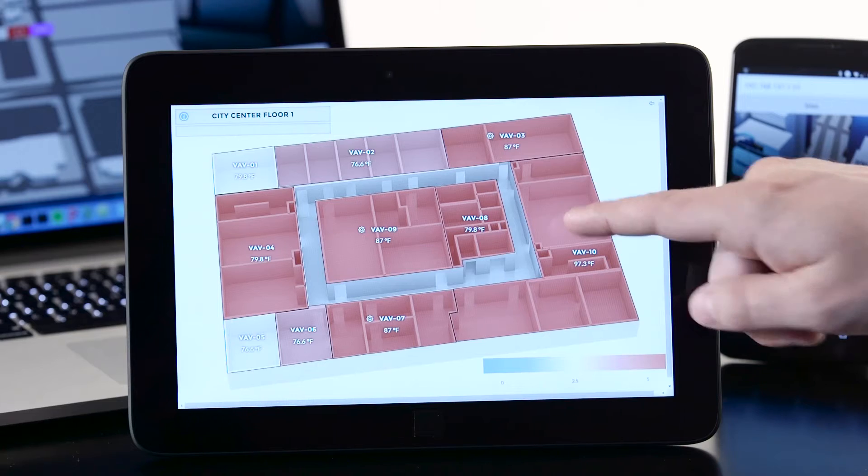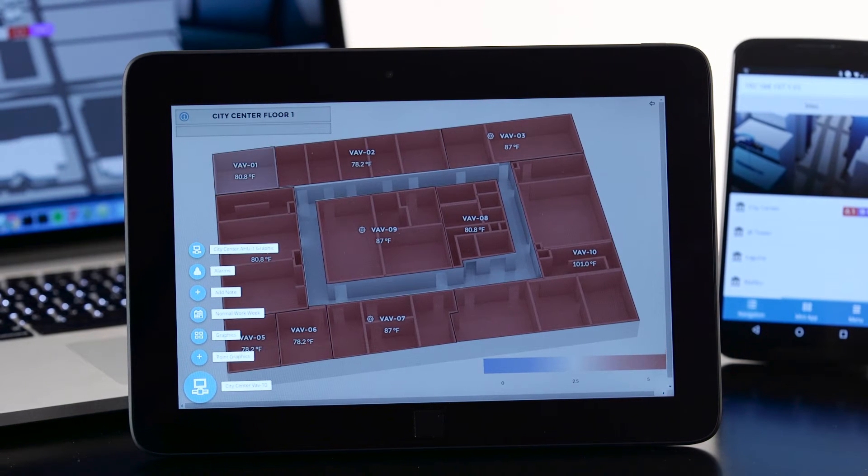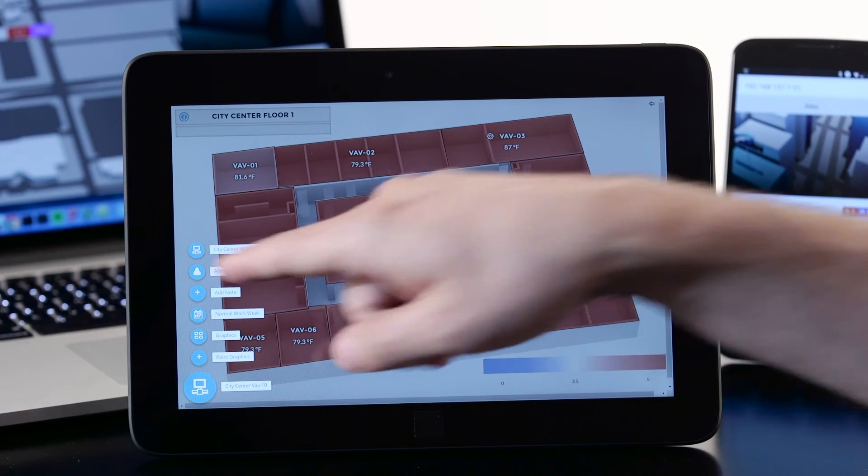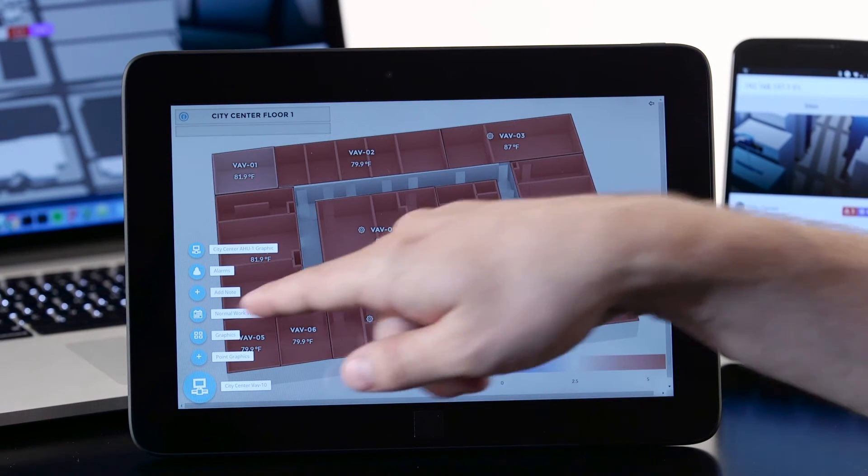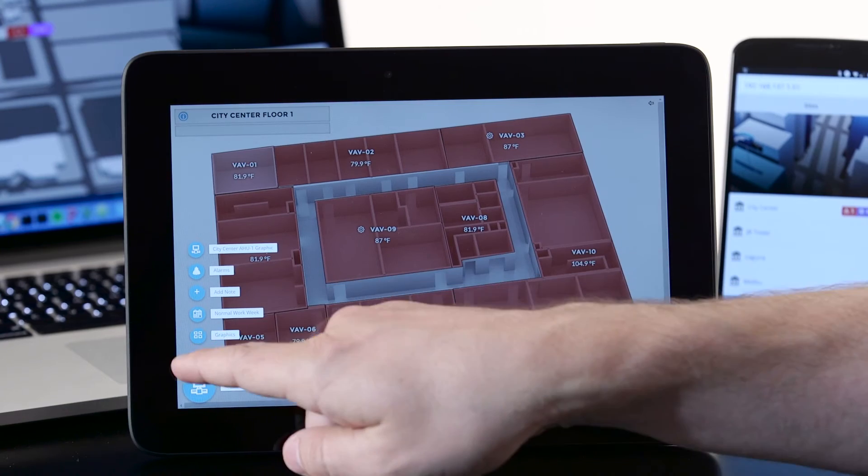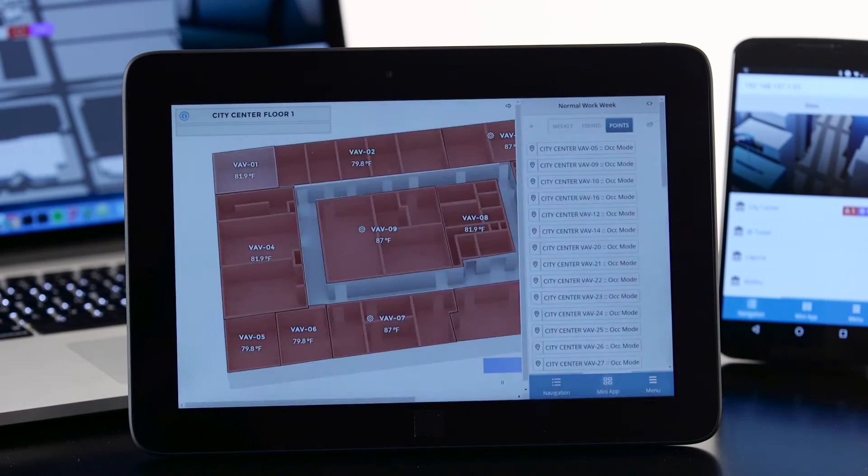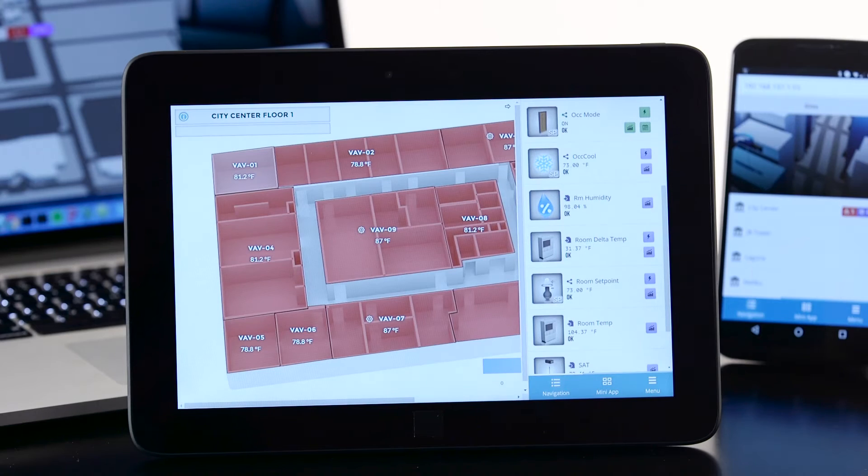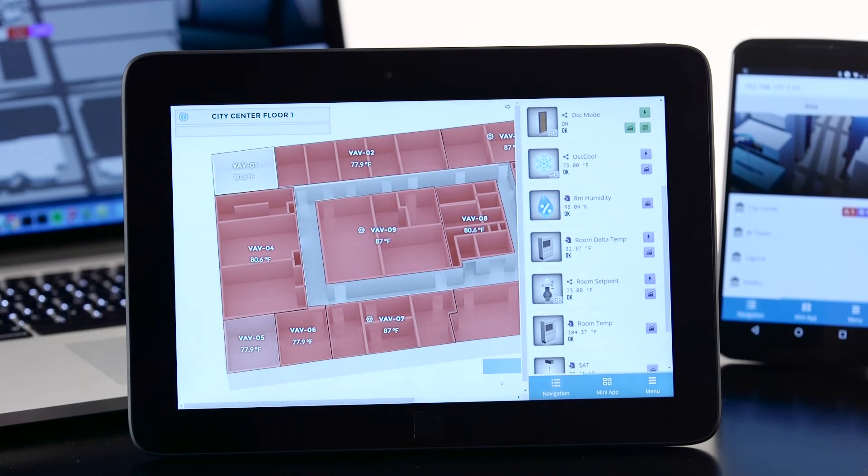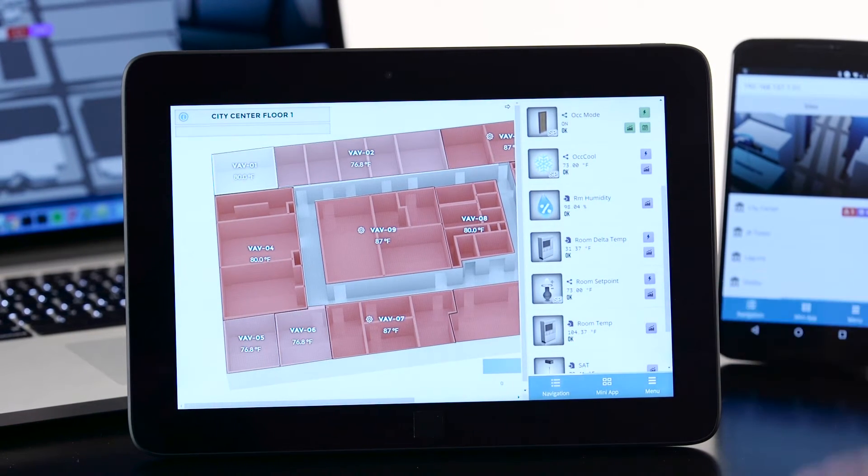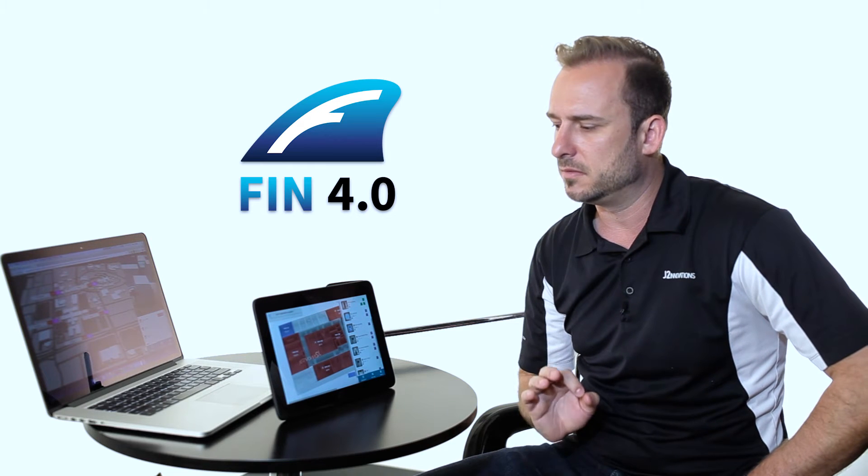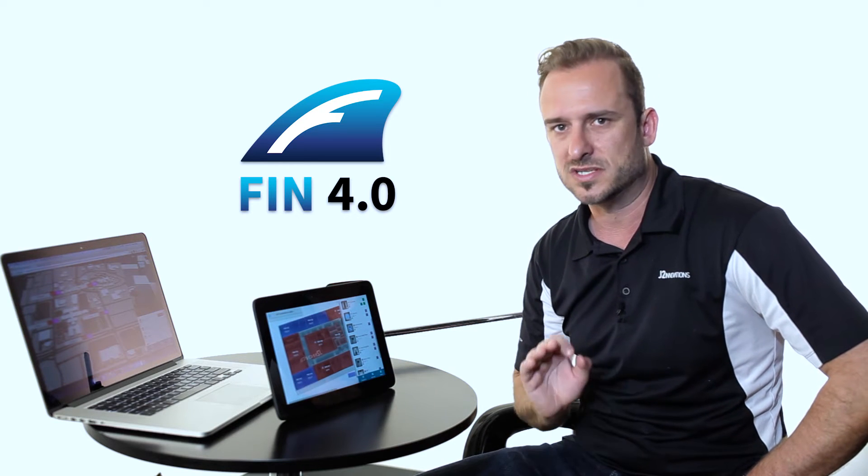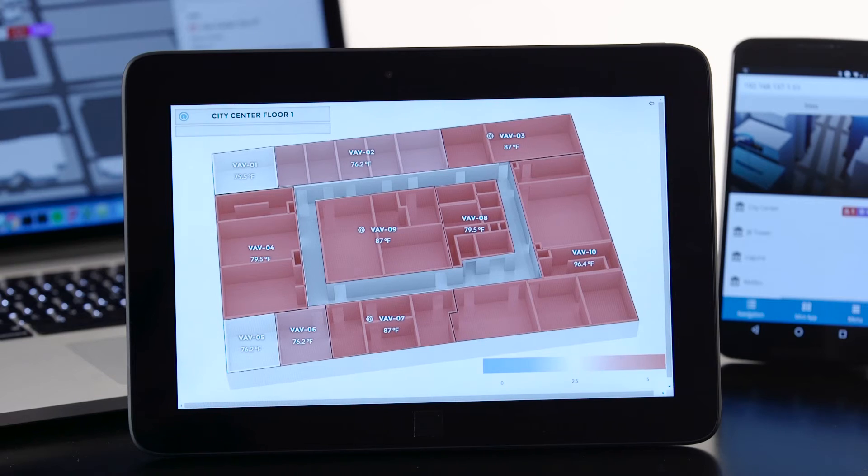So when I click on a different VAV box, you'll notice that the magic bubbles are dynamic. If there's an alarm for that VAV box, it'll show a magic bubble for the alarm. If there's a schedule, it'll show the schedule, and so on. You could also open up the point graphics for that particular VAV box, and the same experience that you had on your phone is now on your tablet as well. None of this was engineered, by the way. The magic bubbles automatically work based on tags. There wasn't one thing that was done to make that work.